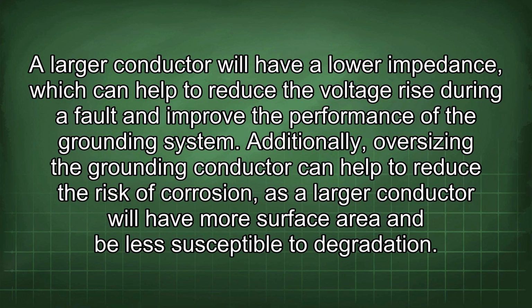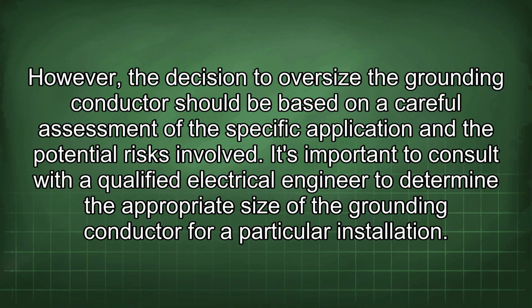Additionally, oversizing the grounding conductor can help to reduce the risk of corrosion, as a larger conductor will have more surface area and be less susceptible to degradation. However, the decision to oversize the grounding conductor should be based on a careful assessment of the specific application and the potential risks involved. It's important to consult with a qualified electrical engineer to determine the appropriate size of the grounding conductor for a particular installation.